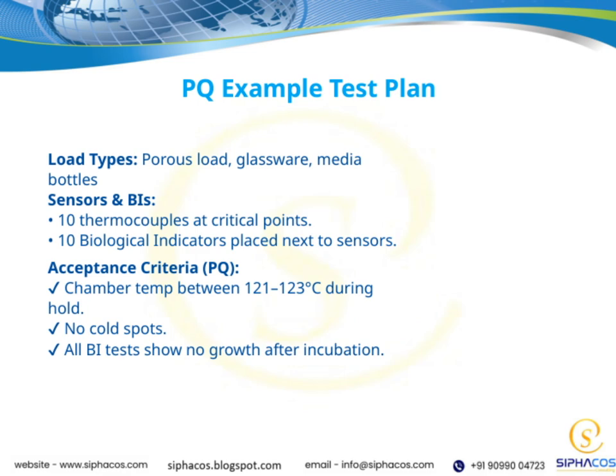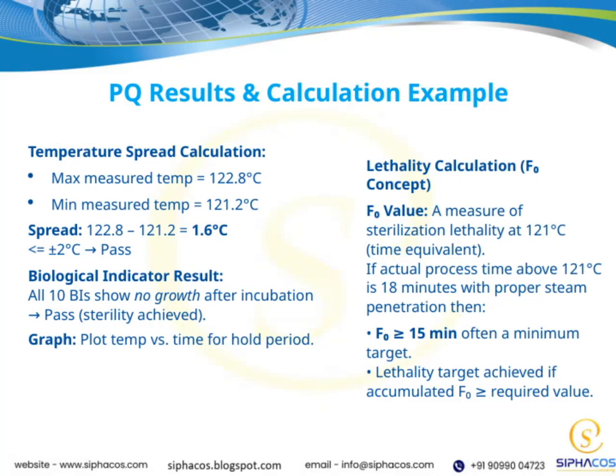Now, let's take a closer look at the lethality calculation using the F0 concept. The F0 value is essentially a measure of sterilization lethality at 121 degrees Celsius, expressed as a time equivalent. When we have an actual process time above 121 degrees C, say, 18 minutes with proper steam penetration, we typically aim for an F0 of at least 15 minutes, which is often considered our minimum target. The key point here is that we achieve the lethality target when the accumulated F0 equals or exceeds the required value for sterilization.